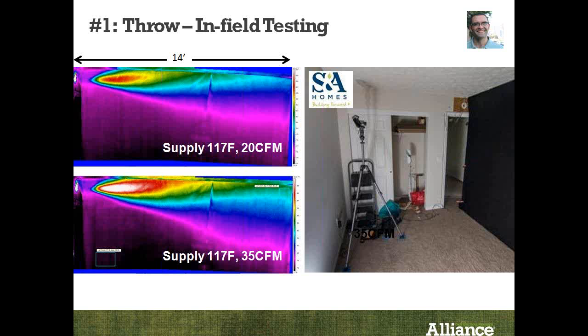And you can see right here we have two different flow rates listed with the same supply air temperature, 20 CFM and 35 CFM. And in both of these cases, you actually get pretty good mixing and pretty good throw all the way to the end of the room. This was a 14-foot room, and so 20 CFM to reach and fully mix a 14-foot room is pretty good. And it's something that you simply couldn't do with a traditional high wall kind of diffuser. Like a 4x8 diffuser. Yeah. We have some other illustrations showing that the air just kind of falls out.